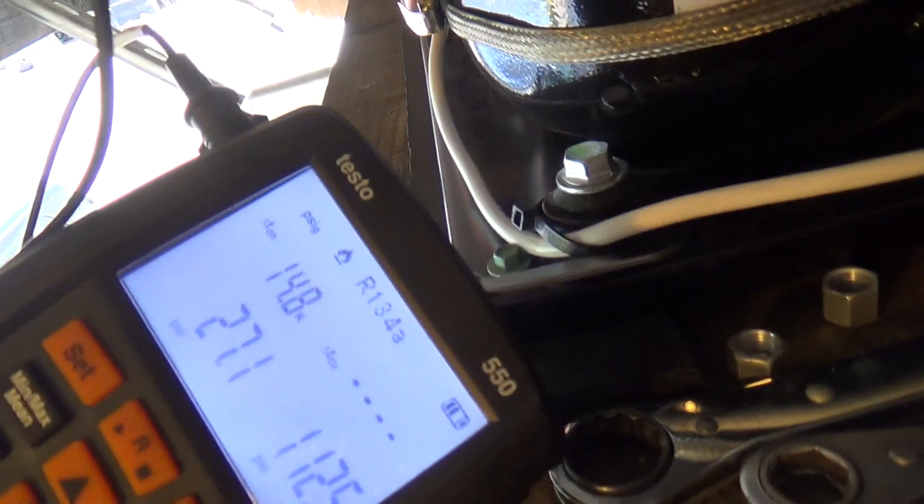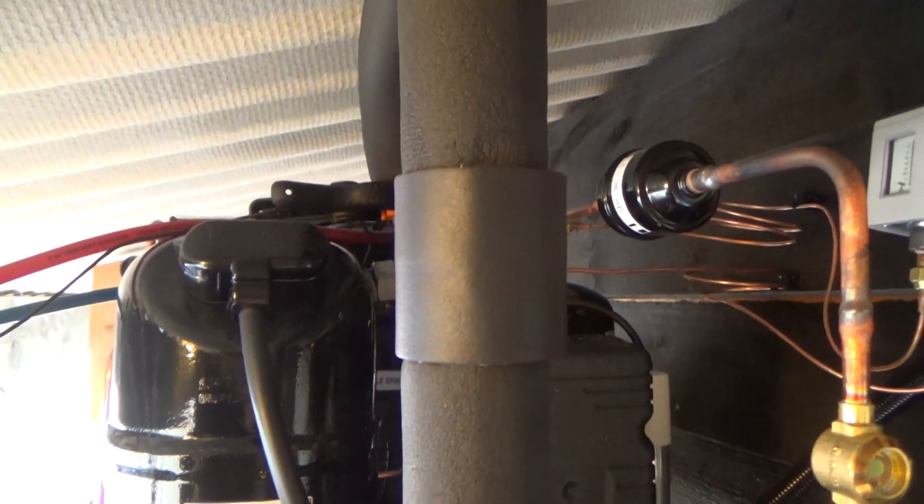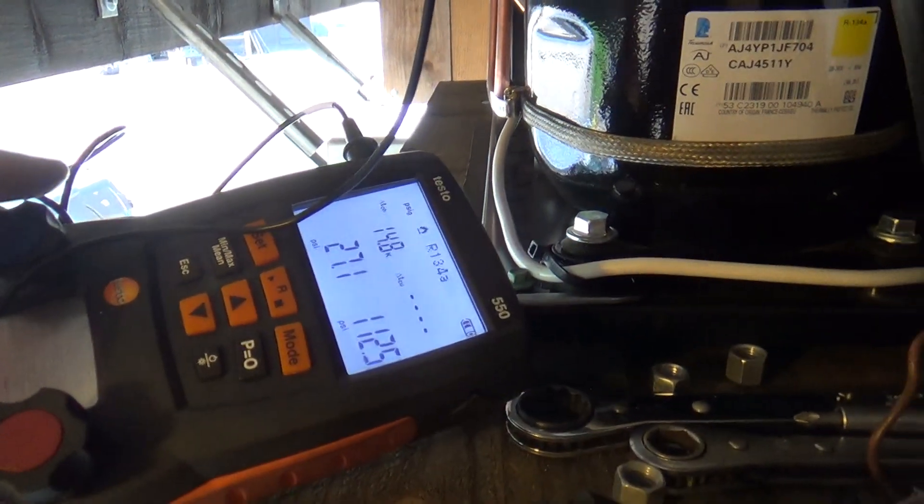I'm running about 14.8K superheat on the suction. It's a good ballpark figure. I don't think the expansion valve is too far after that.